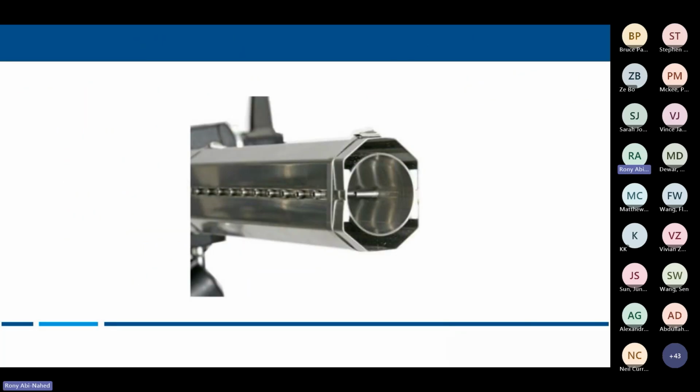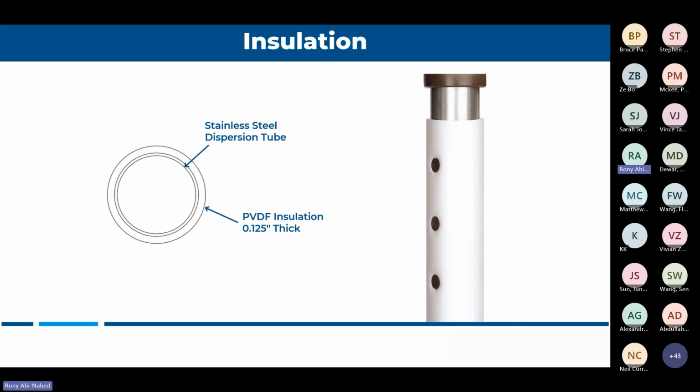Now there's other brands that you will see, like they will have double wall stainless steel similar to the one I showed before, but there's no insulation between them. So that's an air gap that they leave. They're about, I believe, 66, 67% efficient. Another brand will just use the PVDF insulation, kind of the black one I was showing earlier, but theirs is white, but they don't encapsulate with stainless steel.